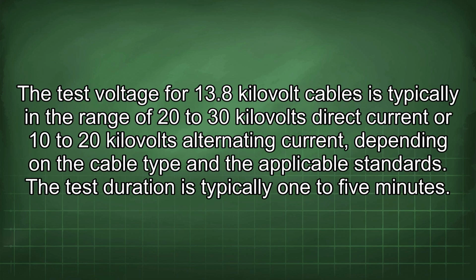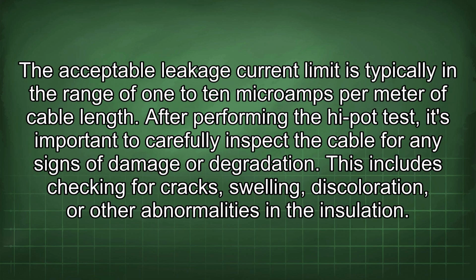The test voltage for 13.8 kV cables is typically in the range of 20 to 30 kV direct current or 10 to 20 kV alternating current, depending on the cable type and the applicable standards. The test duration is typically 1 to 5 minutes. The acceptable leakage current limit is typically in the range of 1 to 10 microamps per meter of cable length.